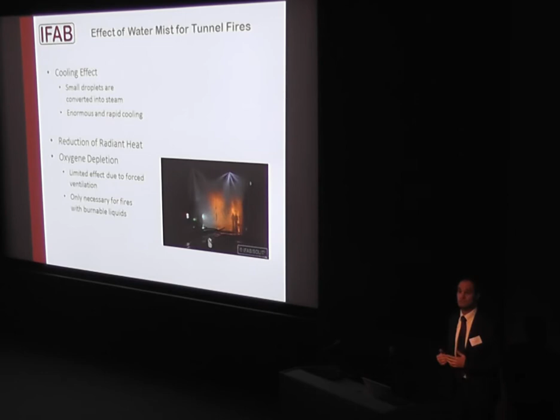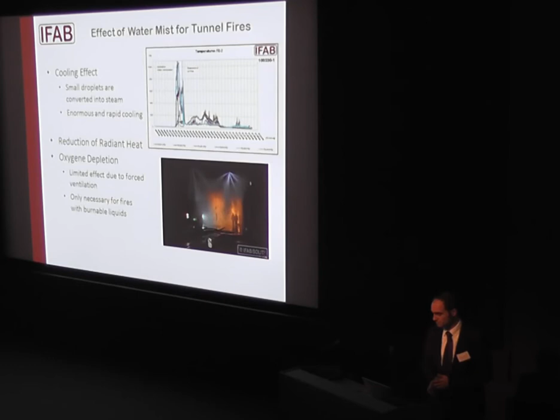What is always said about water mist is the so-called oxygen depletion effect: you vaporize water, creating a larger volume around the fire, which slightly reduces the oxygen concentration. This is a limited effect for tunnel fires because we always have forced ventilation in tunnels. It can only really be used for pool fires, and for solid combustible Class A fires it has no effect at all. That was the graph for the cooling effect.